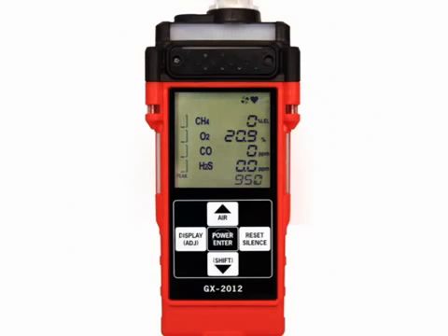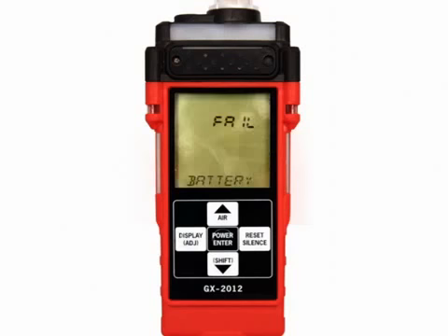The GX2012 is not operational as a gas monitoring device during a dead battery alarm. Take the GX2012 to a non-hazardous area. The GX2012 is fully functional during a low battery warning. However, the GX2012 has only 2 or 3 hours of operating time left after the low battery warning has been triggered. If a sensor failure occurs, determine which sensor has triggered the sensor failure alarm.